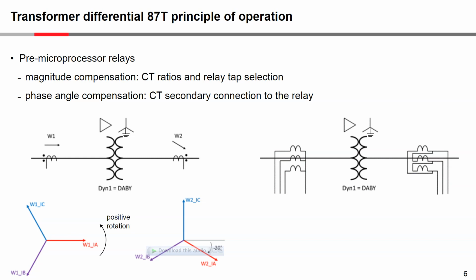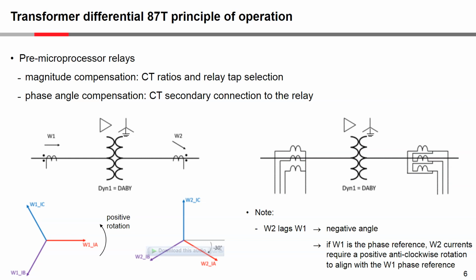Just for a note here, so we understand the referencing: if winding 2 lags winding 1, then that's a negative angle, which means that if winding 1 were to be the phase reference, the winding 2 currents in this particular case would need to have a positive rotation anti-clockwise of 30 degrees to align with the winding 1 phase reference.